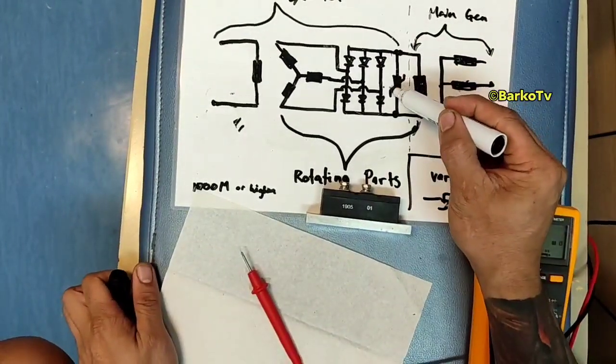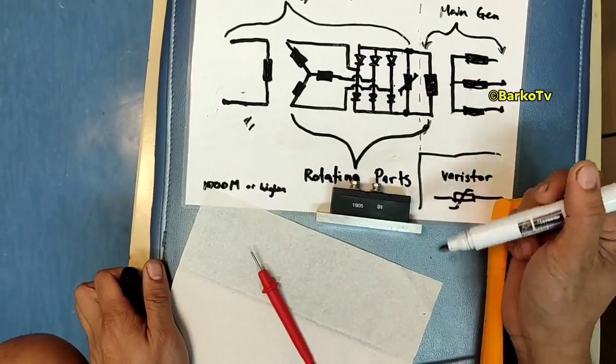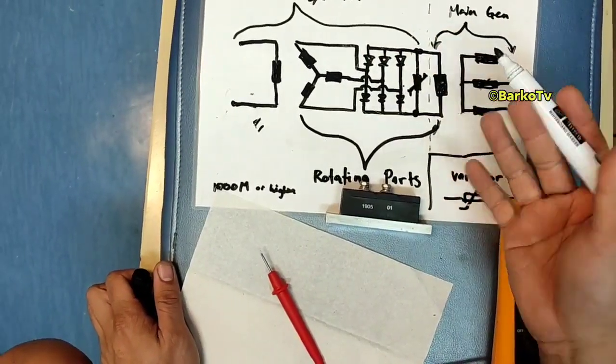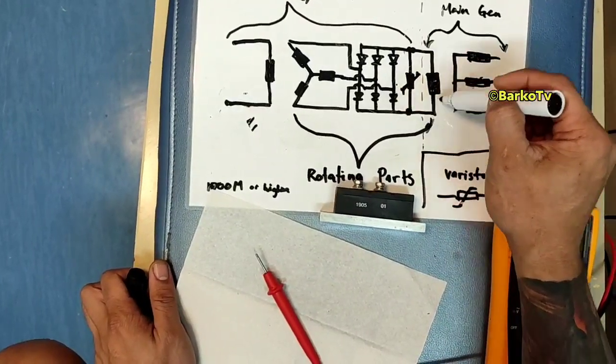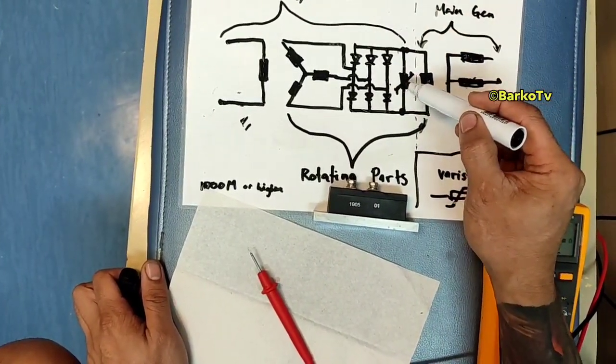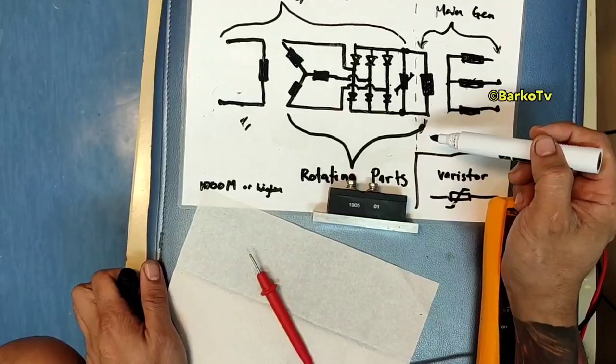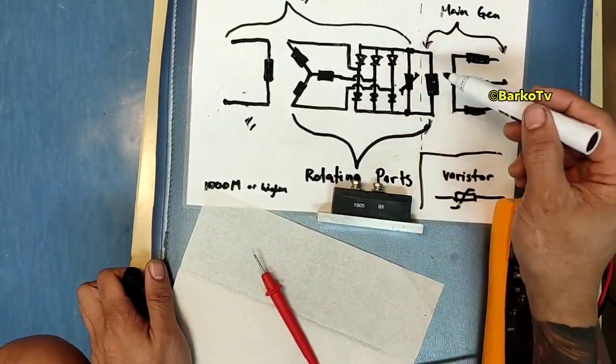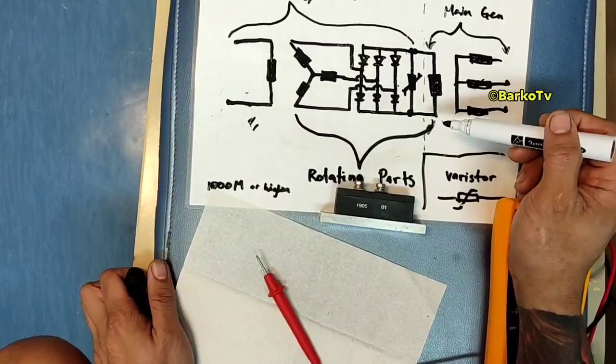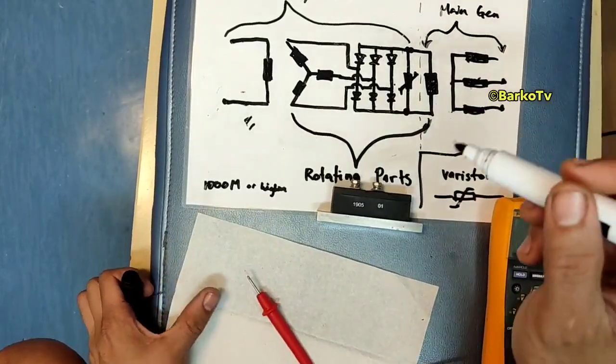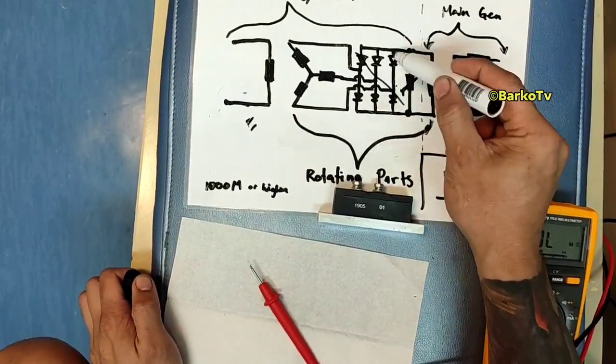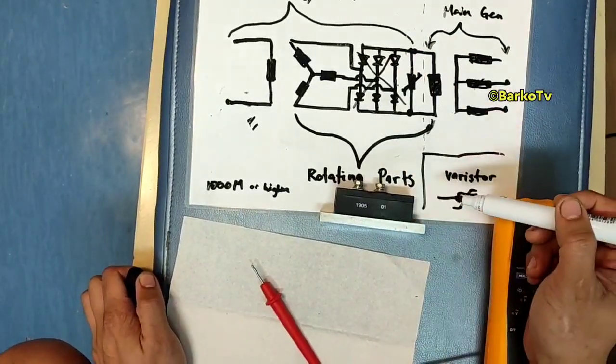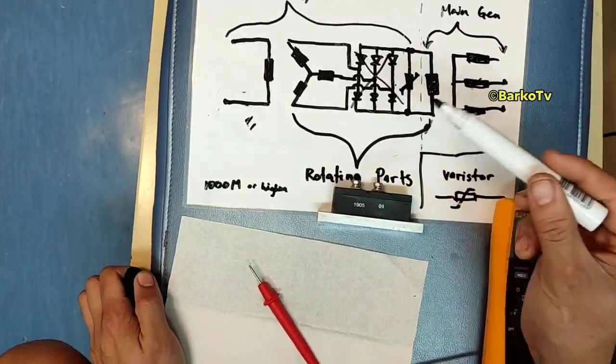How about if this varistor is open. Again, there is no problem. The diode still works, works without varistor. The problem is if you experience high transient voltage or surge voltage, this will damage your rectifier or diodes, rotating diodes.